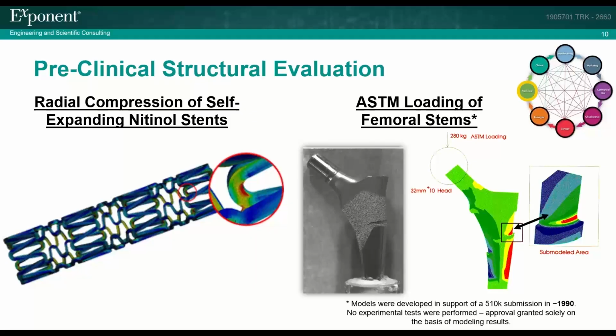Another more common example is the evaluation of femoral stems for either quasi-static or cyclic loading. The example I'm sharing here today is actually quite interesting because it was used in support of a 510(k) submission dating all the way back to 1990. For that particular application, no experimental data was issued, and the device was actually approved solely on the merits of the results provided from the computational models. So it's a unique example in that it dates all the way back to 1990, and that it was successfully used for a 510(k) submission.